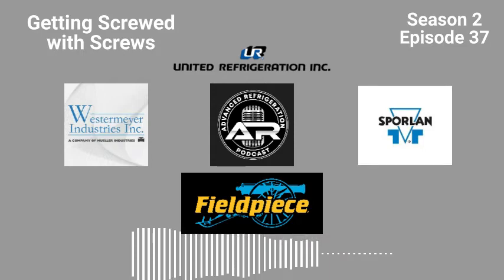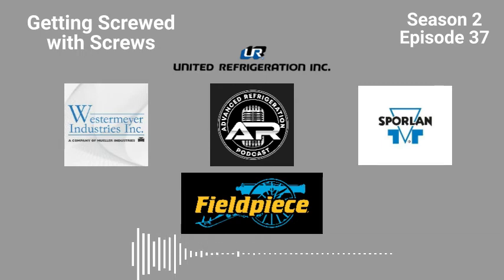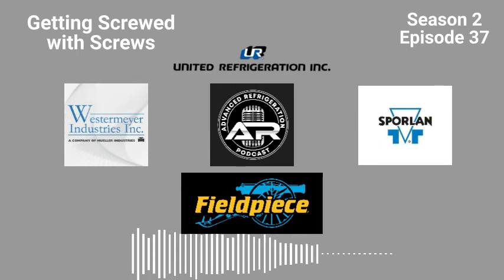Well, I go to start up these 7 brand new freezer coils. Every single coil is wired differently from the factory. Sweet. Not one coil was wired the same, and they all have the hanging evaporators. Yes, the hanging evaporators. So they all have these sweet new controllers in them. You need a 0 to 10 volt signal to modulate the fans. Wait, what? Yes, the evaporator fan motors modulate all the way down to 470 RPMs with a 0 to 10 volt signal.